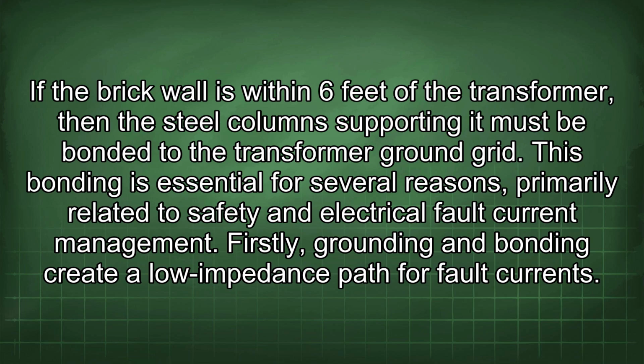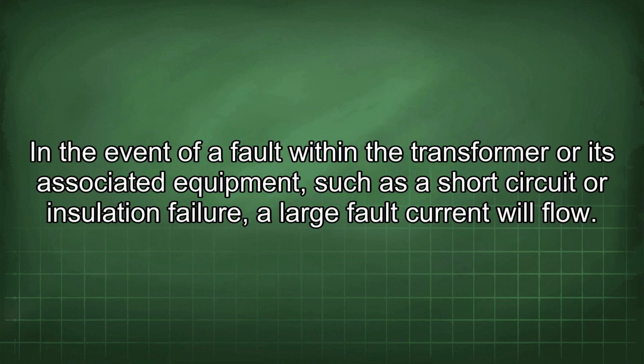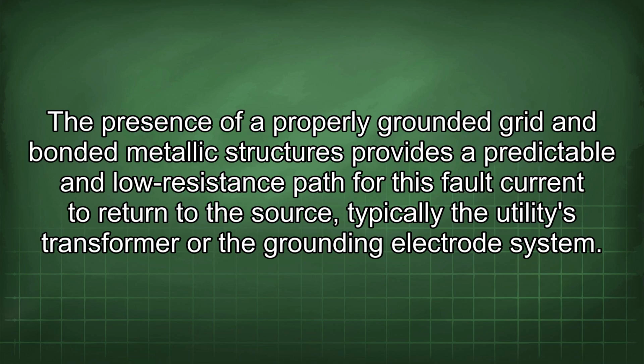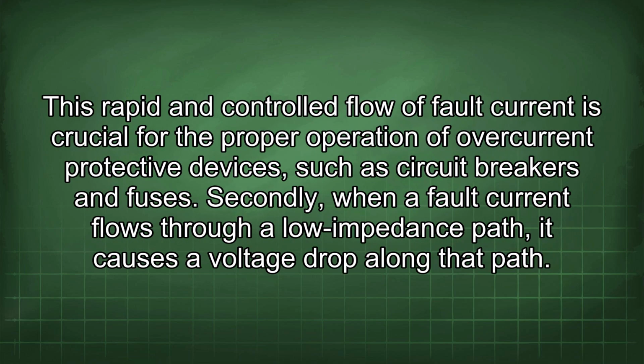This bonding is essential for several reasons, primarily related to safety and electrical fault current management. Firstly, grounding and bonding create a low impedance path for fault currents. In the event of a fault within the transformer or its associated equipment, such as a short circuit or insulation failure, a large fault current will flow. The presence of a properly grounded grid and bonded metallic structures provides a predictable and low resistance path for this fault current to return to the source, typically the utility's transformer or the grounding electrode system.